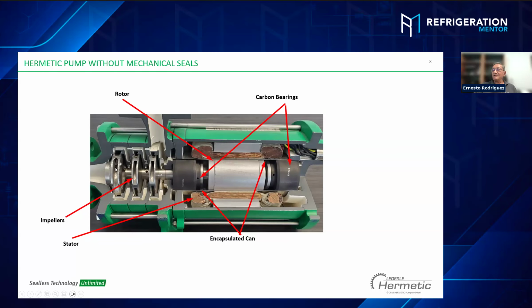Well, basically, the pump, for safety, to avoid the high damage of the impellers, we have the bearings, carbon bearings. When we have the cavitation, we have a lack of lubrication on the bearings. The bearings start wearing down because of this differential and the gap between the bearing and the shaft, the pressure of the pump starts decreasing, and the pump is going to stop. Basically, when you have a problem with cavitation, the main problem is to replace the bearings, and the majority of the time to fix this problem is only bearing replacement and gasket replacement. In very rare situations, the impellers can be damaged, but it's very rare. Basically, the pump stops itself when the bearings are damaged.